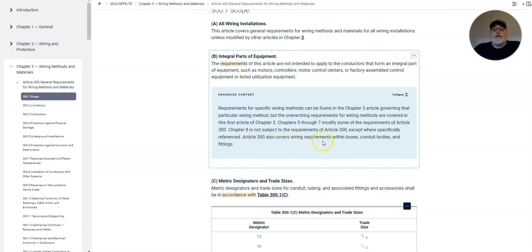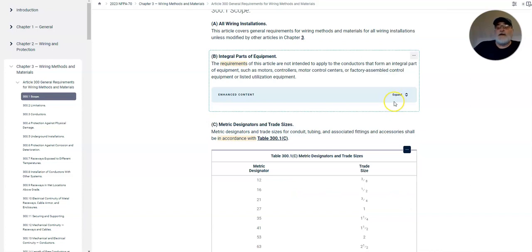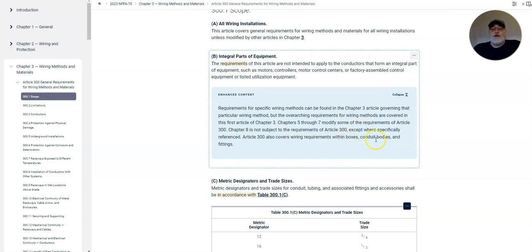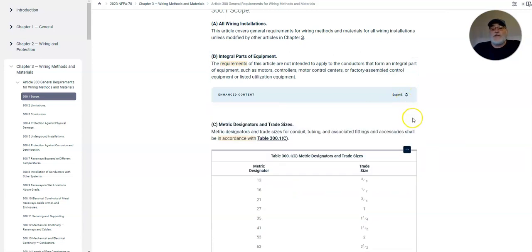Article 300 also covers wiring requirements within boxes, conduit bodies, and fittings. So what does that mean? Basically, for the wiring methods inside of boxes, conduit bodies, and fittings, it is the governing article. This is where you're going to go to find how many wires you can legally and safely put in a box, and how many wires you can put in a conduit body, which is an LB, something that you see outside. We'll go further into the course whenever you see these particular pieces of equipment. And fittings: it talks about different fittings and their different uses.